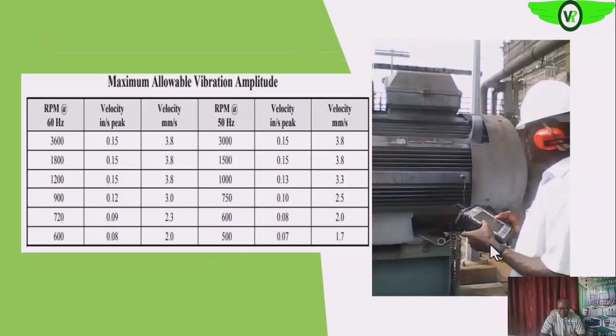Then after installation of the equipment, you can check the vibration levels. The vibration level should be within tolerable limits as specified by the equipment manufacturer or by your facility. In the absence of that, you can use the table here as a guide to ascertain that the equipment is not running beyond what is acceptable or tolerable. Once the vibration is too high, it affects the operations of the equipment.